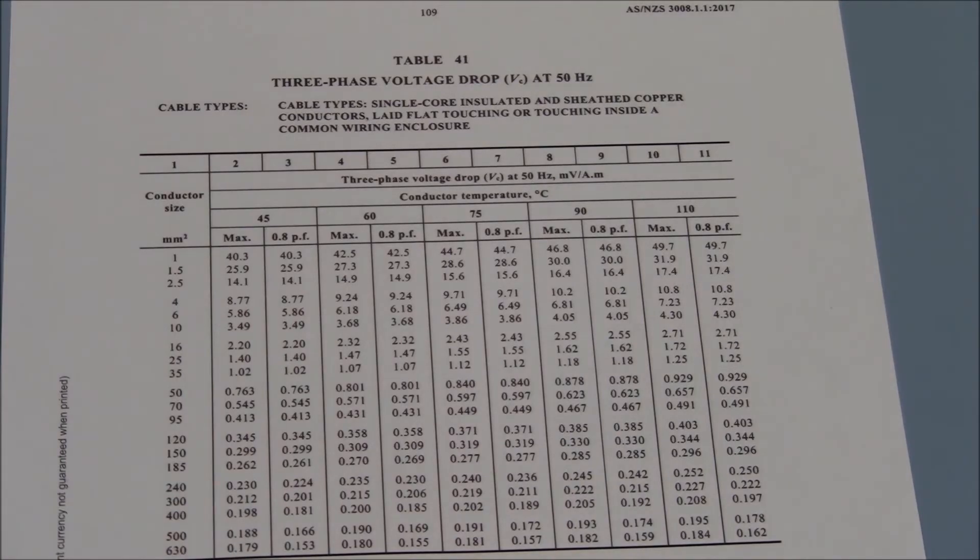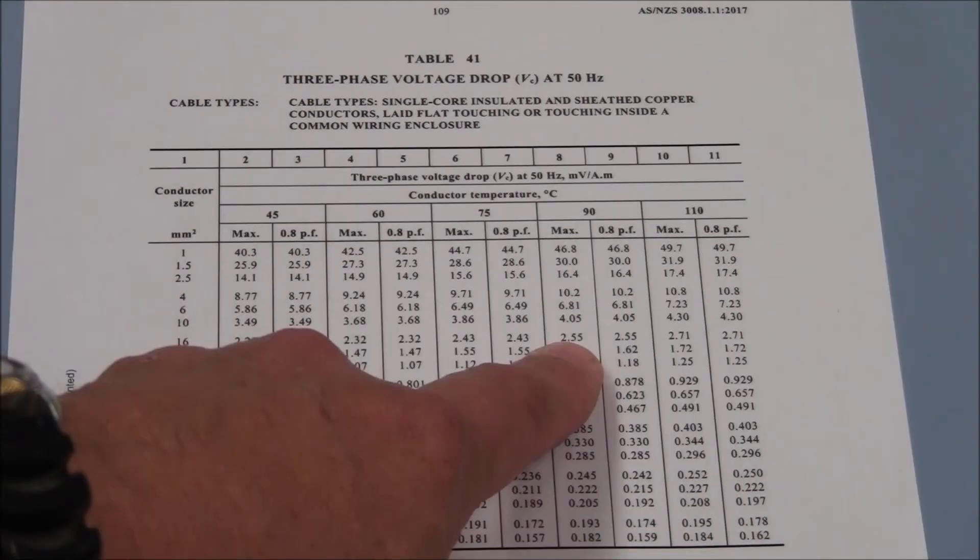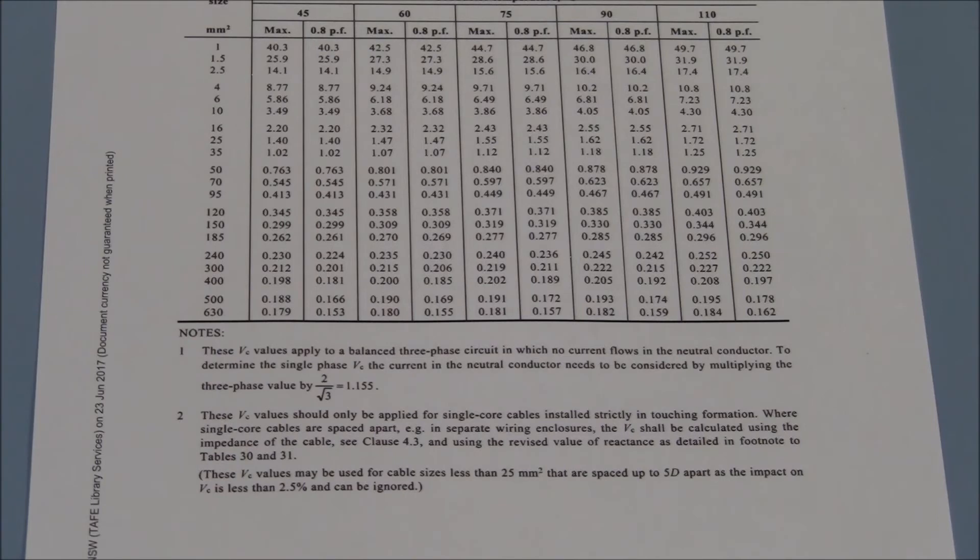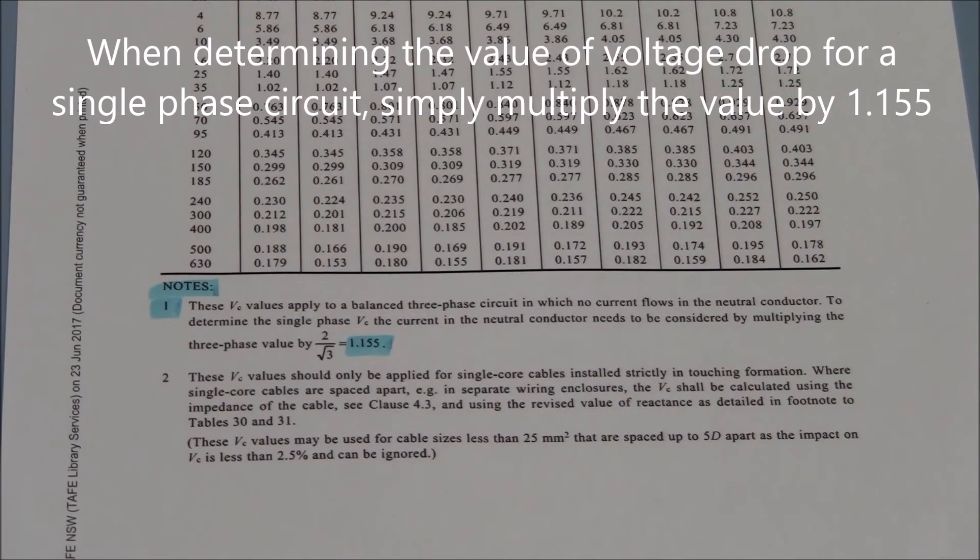Consulting table 41 column 8 for 90 degree, the value of VC is 2.55. However, as this is a single phase circuit we need to convert this three phase value by multiplying it by 1.155 as per the footnote at the bottom of every voltage drop table.